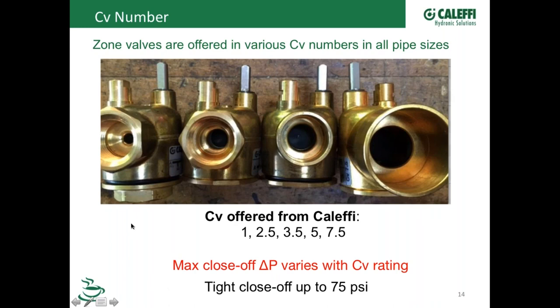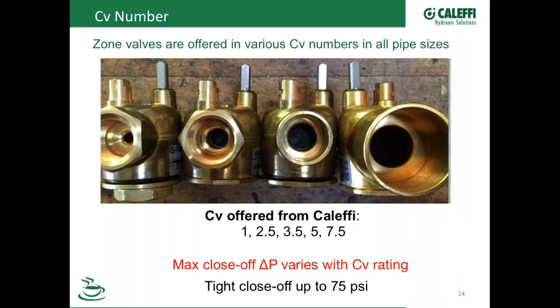Cody and Greg and any of us really can help you make sure you've got the right selection. And maybe I should have cleared that up a little bit on the front end. This symbol right here, delta, is the fourth letter of the Greek alphabet, I think. It really refers to difference or change. So when you see a delta in front of a P, that means pressure differential, the pressure differential that that valve is closing off against. You'll see this little delta sometimes in front of the letter T for temperature differential, through a boiler, a heat exchanger, or a pump that works on a delta T type of application. So that's just to clear up that delta so you know what we're talking about here.